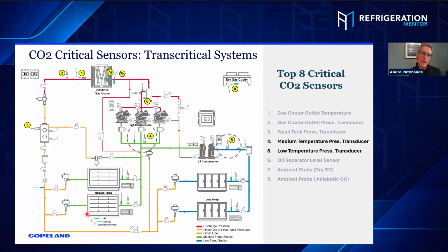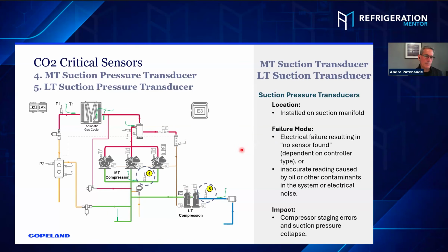So those are the three main ones related to the high pressure valves and bypass valves and gas coolers. Now, as a group, we said there's a couple more that are super important. The medium temp suction group pressure transducer and the low temp suction group pressure transducer. And their mitigations, of course, are going to be exactly the same because they both manage a suction group. So they're sitting on the manifold, of course. Failure mode, no sensor found. You might, though, have some inaccurate reading if you get some oil or some contaminant in it. So that's possible. And the impact: compressor staging error or suction pressure collapse.